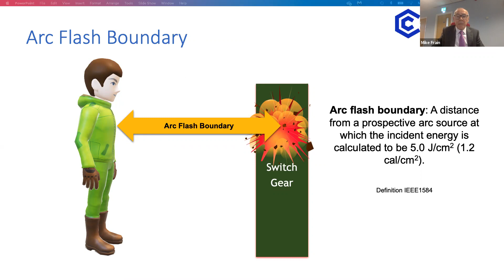Just flick through these. This next slide illustrates the incident energy exposure when carrying out the calculations, the working distance used from head and torso to the prospective arcing source. Next is the arc flash boundary, and this is the distance from a prospective arc source at which the incident energy is calculated to be 5 joules per square centimetre, or 1.2 calories per square centimetre. That's what we mentioned earlier.